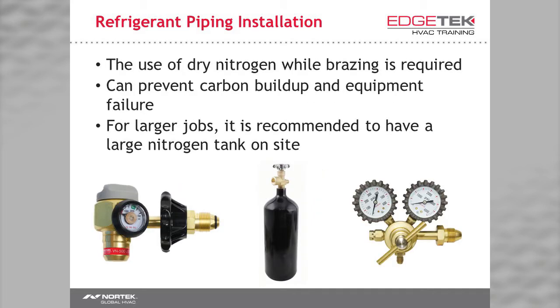See that black tank in the middle? That's the thing everyone says they use all the time. If you use it, please continue to do so. If you don't use it, well, I don't really have anything nice to say. It's nitrogen. Anytime you're brazing, use nitrogen. For your pressure tests, use nitrogen. You know, dry nitrogen. You need a regulator that can handle a pressure test of 550 psi, so it'll probably say about 700 psi on the gauge.